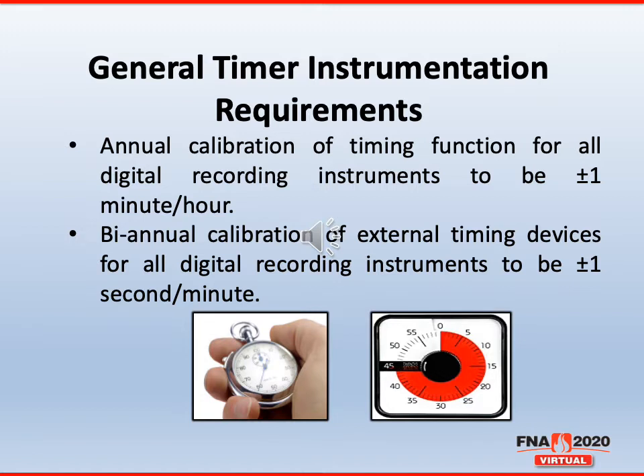So if you have a documented procedure that states we have a system in place such as the digital synchronization of timing systems to NIST, this would be acceptable. Furthermore, they are requiring a biannual calibration, so every 2 years, of any external timing devices for all digital recording systems to be plus or minus 1 second per minute. So if you have a timer or a clock or something that's on your furnace for your times at temperature, these items will need to be calibrated once every 2 years.